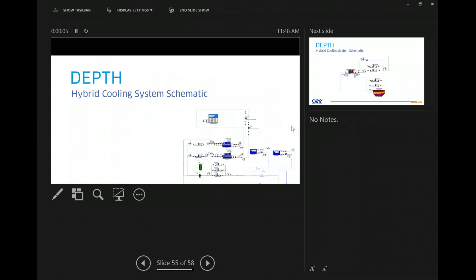So I won't get into too much detail, but the hybrid system basically has, we've tied part of the cooling system to the ground loop through a heat pump chiller, and that'll be our primary source of cooling. But we've also got heat recovery chillers and a fluid cooler or cooling tower tied to those chillers, so this is more of a traditional cooling system. We only use the geothermal loop as the primary source. I can't remember exactly when we switch over, but when we get higher loads, we start using the traditional system so that we don't overcool the ground. We're overheating, sorry, we're dumping heat back into the ground in the ground source system.